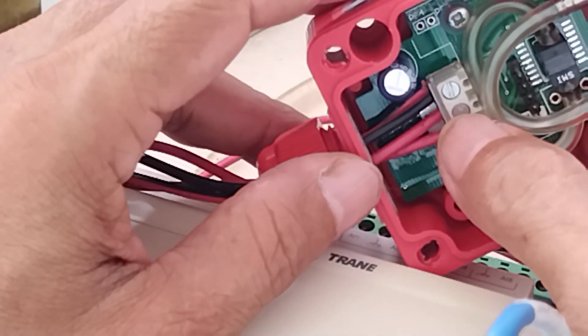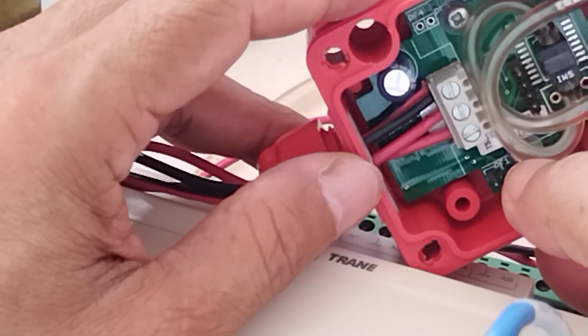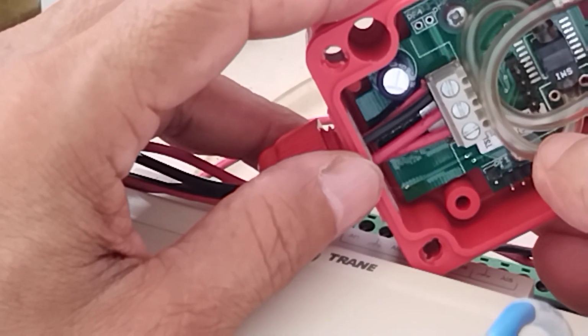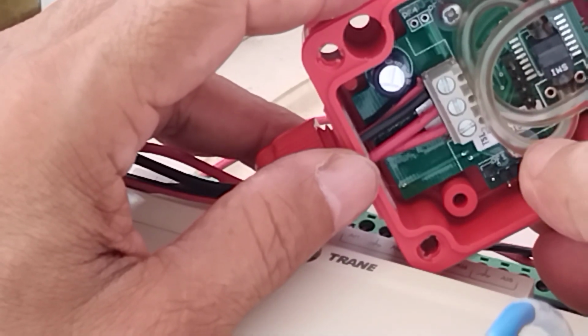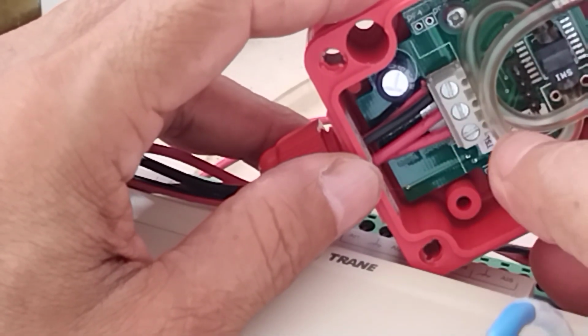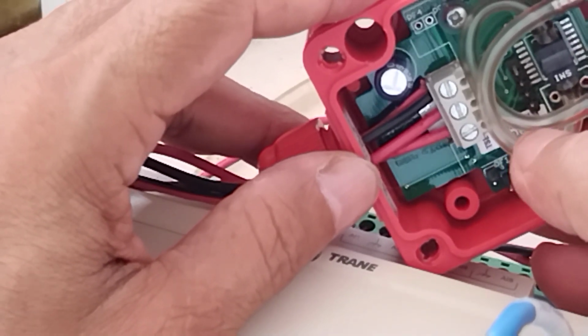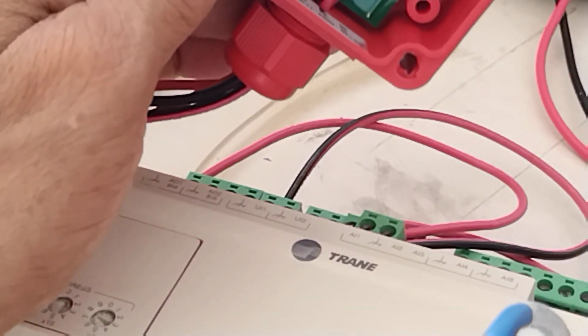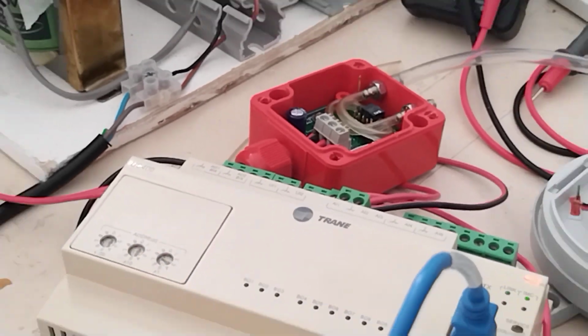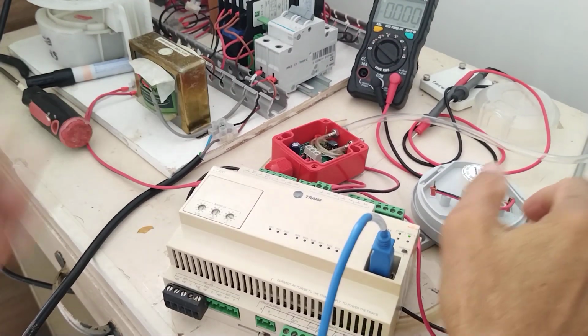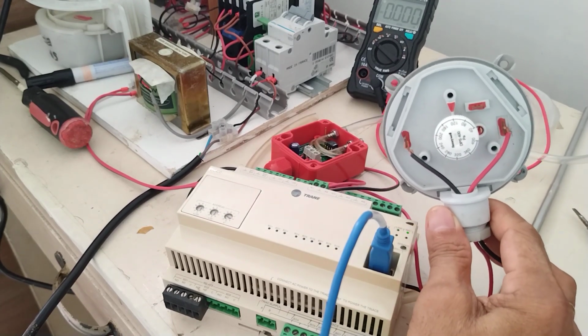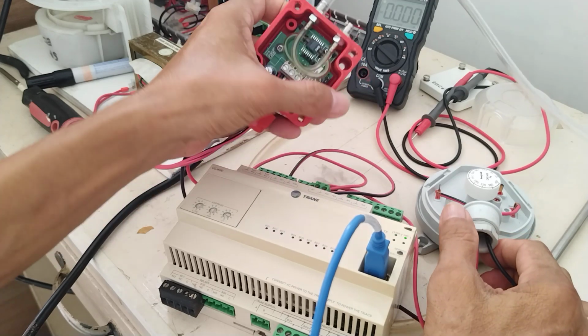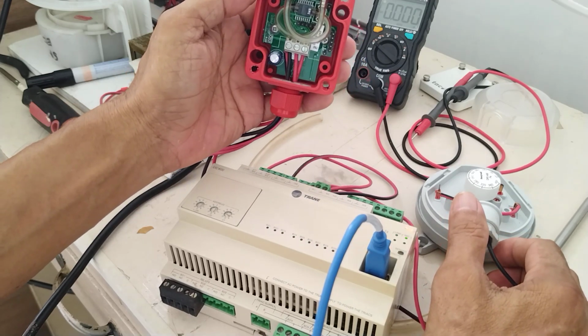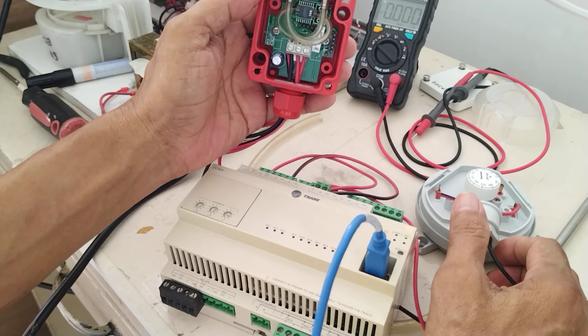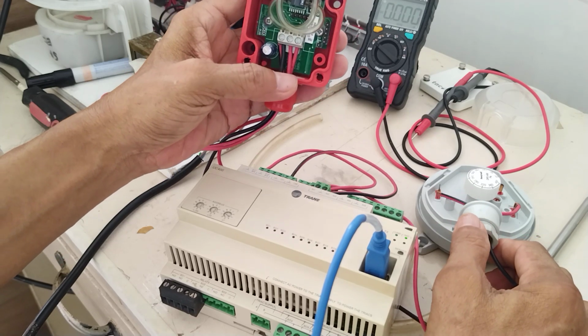Then 3 and 2 are for the signal output for the differential pressure reading, okay? So it will be 0 to 10 volts. Then you have to do some scaling in your system, okay? So I need one cable here, 2 core. I hope it's clear. Okay, so I need 1 cable, 2 core here. Then, I need two cables, two cores. Meaning, if you can find a cable with four cores, then you can use it here. Now actually, you don't need any shield here.